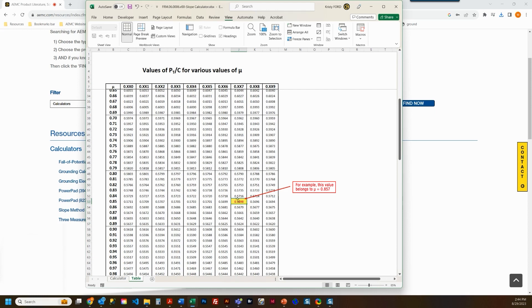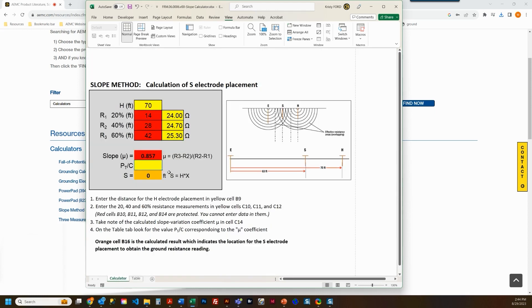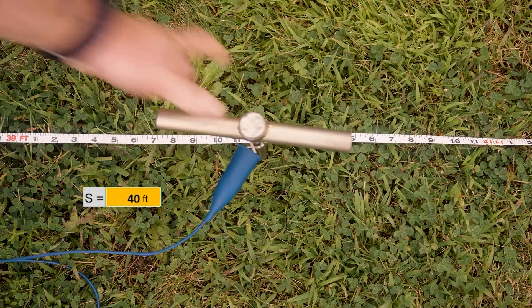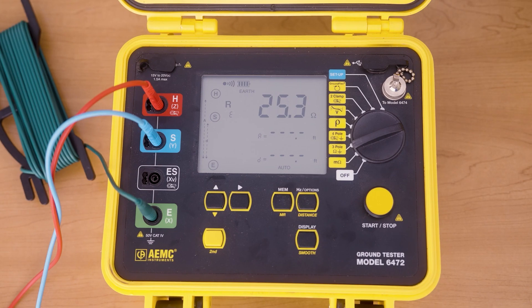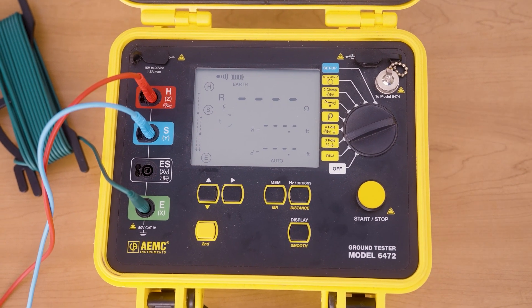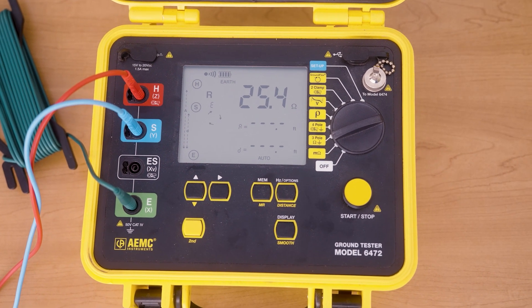At this point, we have located the decimal multiplier using the table. Add the decimal multiplier to the calculator to establish the last measurement, which will be the effective system resistance. This will now show you the calculated distance of the S electrode placement. In our example, the S electrode should be spaced out to 40 feet from the ground system under test. The S calculated value is displayed in the orange cell. Now that we have our S electrode distance, let's take a final measurement. We'll place the S electrode at the calculated value to get the effective ground resistance of the system. Here, the effective resistance value of the system is 25.4 ohms.